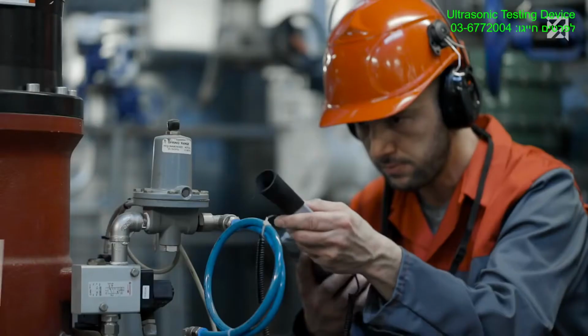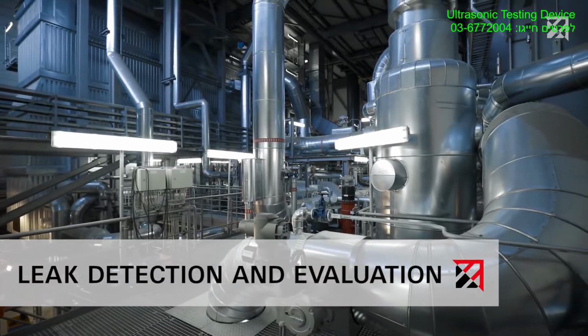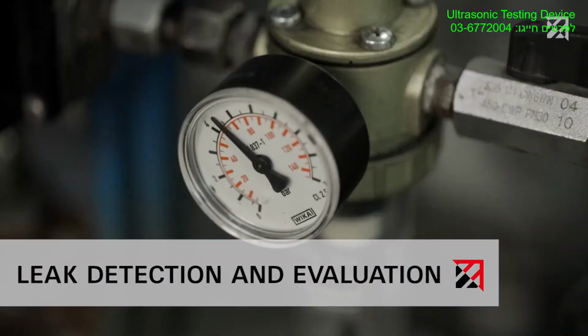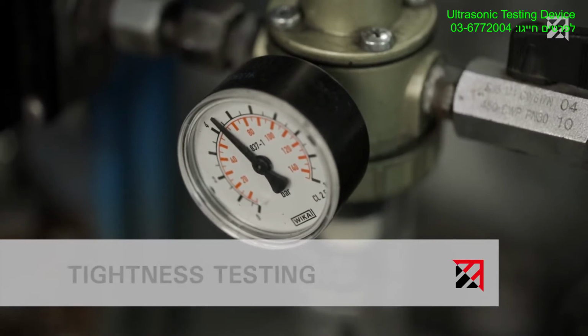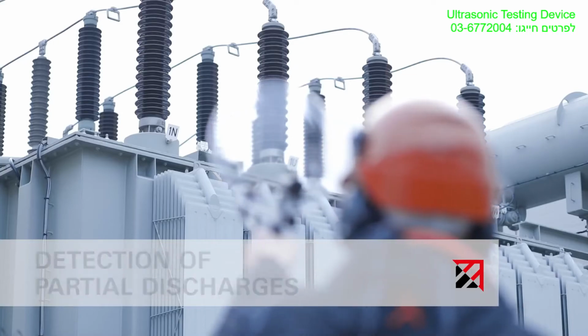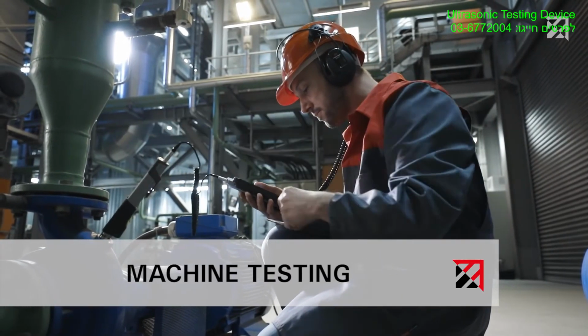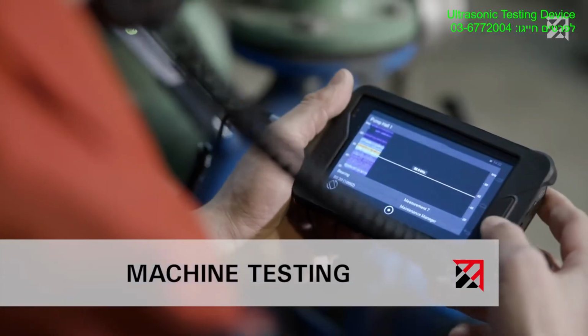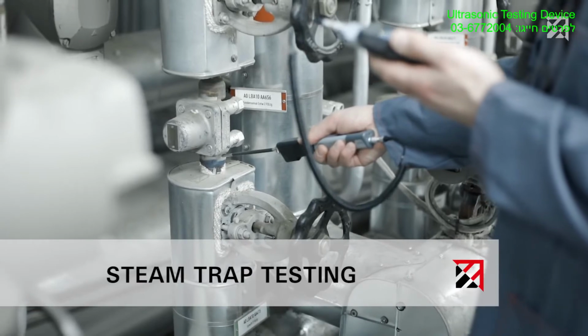The powerful testing device is used in combination with an airborne sound sensor for the detection and evaluation of leaks in compressed air, gas, and vacuum systems, as well as for tightness tests. It can also be used to test electrical systems. With a combined structure-borne sound and temperature sensor, the state of machines and systems, such as rolling bearings, ball bearings, or steam traps, can also be established.